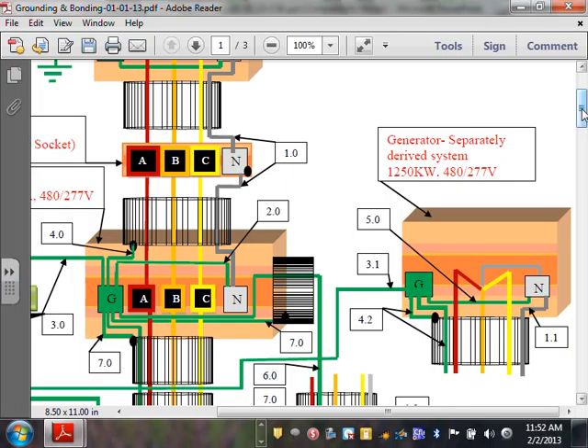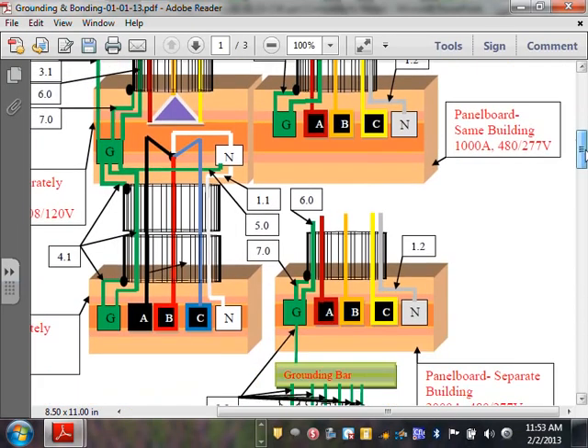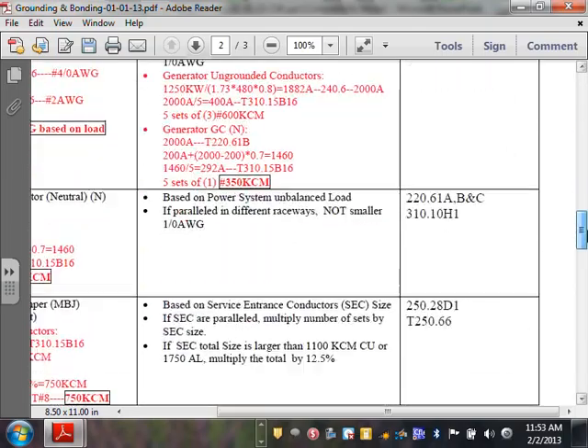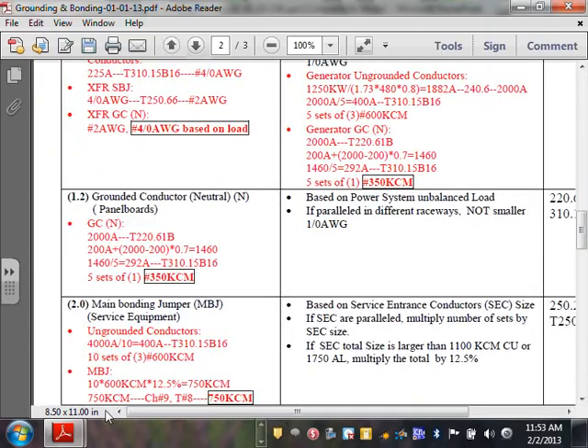And you can see that number 3.1 is going all the way back to the ground bar here. It could also be landing on the steel of the building because it's bonded. And then I pulled 4.2, guys. These two little things, 4.2. These are called supply side bonding jumper, believe it or not, out of all the terms. So let's go to 4.2, will you?